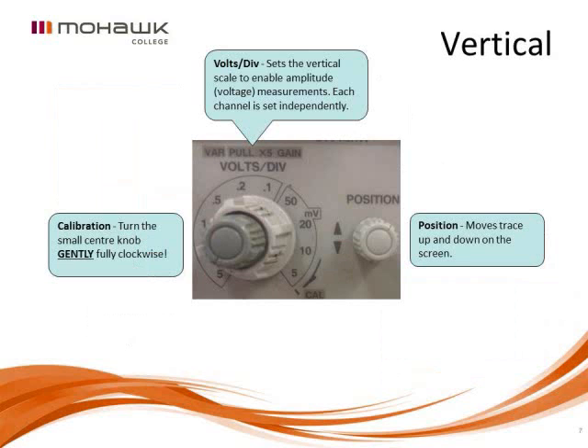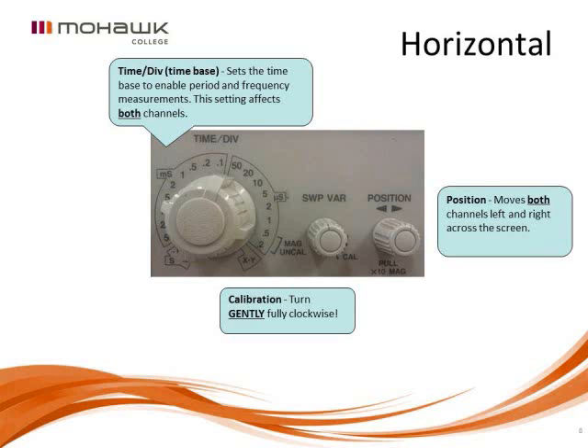The vertical control sets the volts per division. The actual settings will vary on the oscilloscope — for example, you might set it to one volt per division, which means one vertical square on the screen represents a change in voltage of one volt. The calibration knob in the center must be turned all the way clockwise; otherwise the display is uncalibrated and your readings will be incorrect.